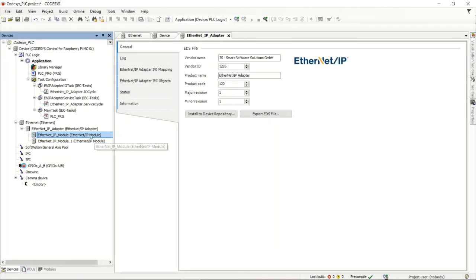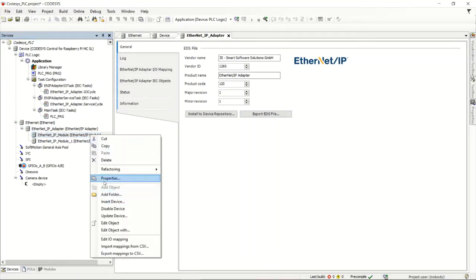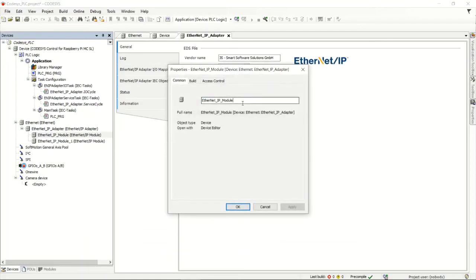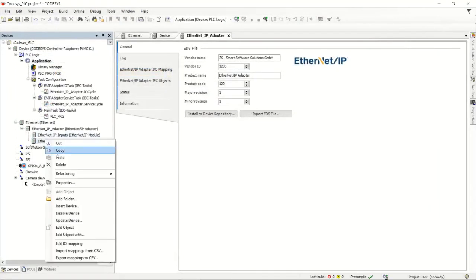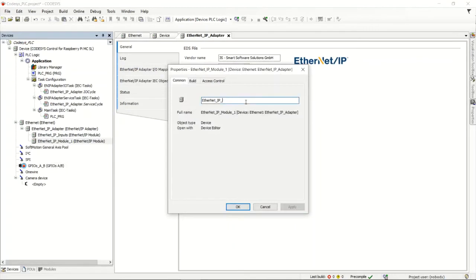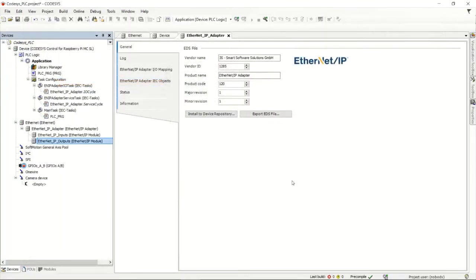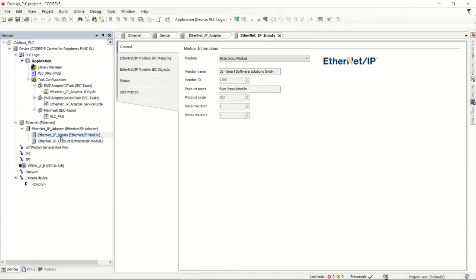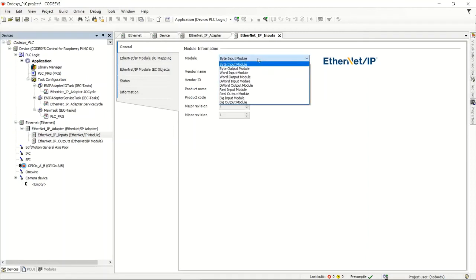Next, I'll configure the input and output modules. First I'll rename them — I'll call this one 'EtherNet IP Inputs'; it'll refactor the name. Then I'll rename the other to 'Outputs' so the names are meaningful. Going into the input card, a couple of things are important: you have to configure the size. You can choose all the different sizes available, and in this case we're going to be using a double word, so I'll select the double word input module.